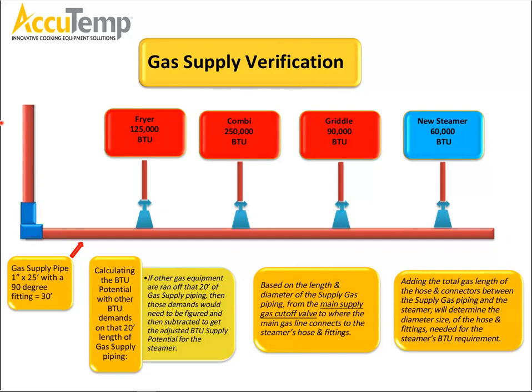And that total pipe length, from here to here, is going to be 25 feet. Now, as we said, we have a 90-degree fitting, and going back to the other slide, it's going to equal 5 feet. So we have a total of 30 feet. Now, two slides ago, I said remember that number: how many BTUs can a 1-inch pipe support at 30 feet?